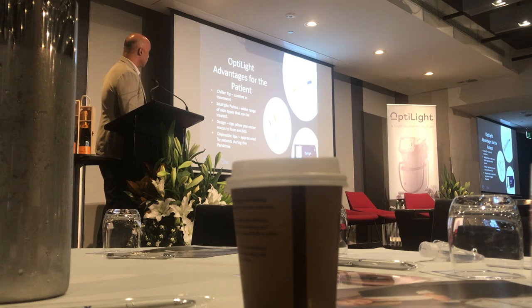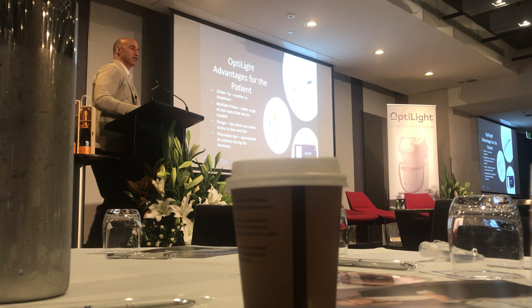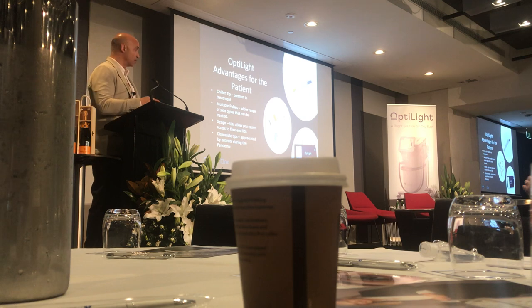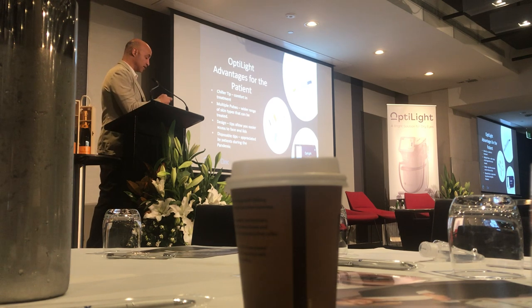It's FDA approved. There's a disposable tip — the OptiLight will not work unless you put the disposable tip on, and you shouldn't try without it. The outer circular circumference has a metal cylindrical cone around the sapphire plate. If you actually did it without the tip, you would be burning the skin with that metal.